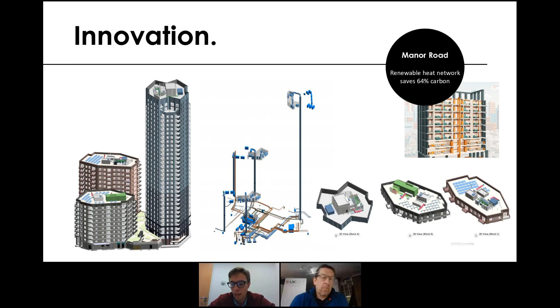You can then explore opportunities, because there are benefits to potentially breaking these neutral or ambient temperature systems down block by block or building by building, because of the delta T of the system in operation. Your ambient system flow temperature is typically around 25 degrees, but your delta T is only around 5 degrees, so your pump energy is significant. I'll come on to a breakdown of energy later on. But that also saved us around 500 square metres of plant space in the first phase alone, by not having a massive central energy centre and using roof space that would normally not be utilized, although it could be utilized for amenity space. But in this project it wasn't, and it was limited in footprint.